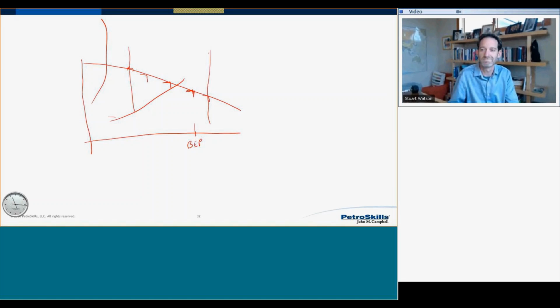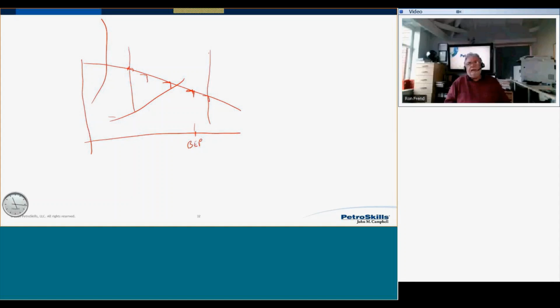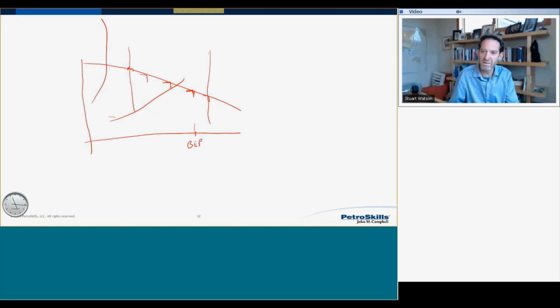I don't think it affects the NPSH curve directly. So the short answer there is no, it doesn't. We test with water because it's very easy to test with. And as you change the SG, the NPSH curve, you can think of that head as energy going into the front of the pump. It's the suction head. And the NPSH is the difference between the vapor pressure and the suction energy. And so if you change the SG of the fluid, the NPSH will be the same.